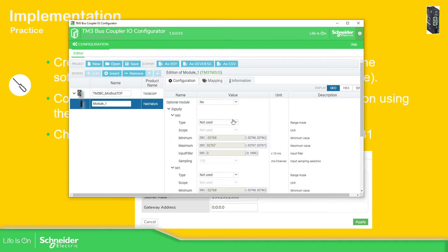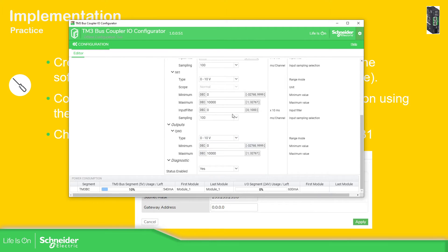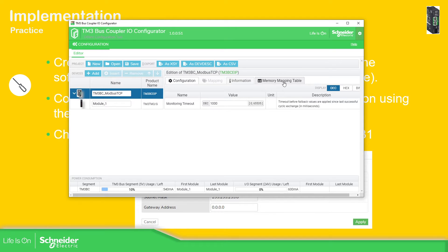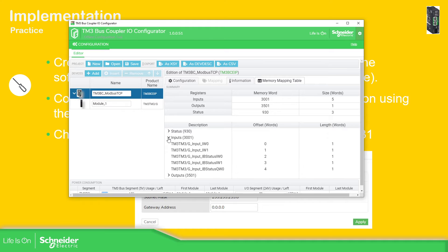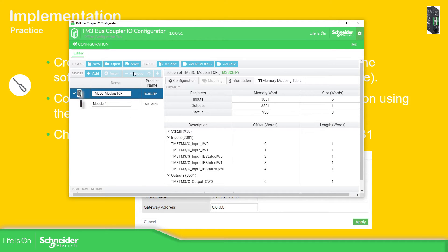Now I'm going to define the configuration. I'll select these two analog inputs as 10V voltage, and the output also as voltage. I have connected this analog input to an analog output of the PLC so we can read it. The important thing here is the memory mapping. Here you can find the defined memory addresses in order to access this information. Under inputs, you can see the offset and the start position for the input. If I want to read from outside, I should access this address plus the offset. The same applies for the analog outputs.